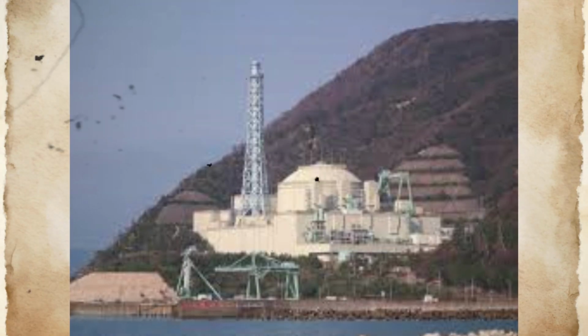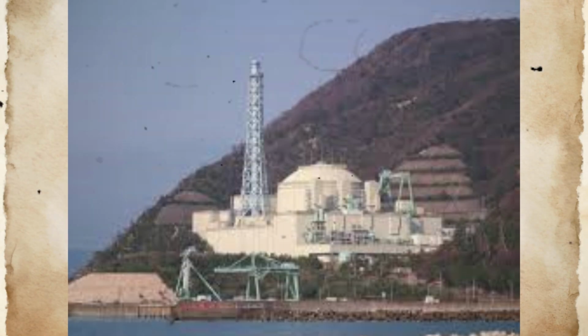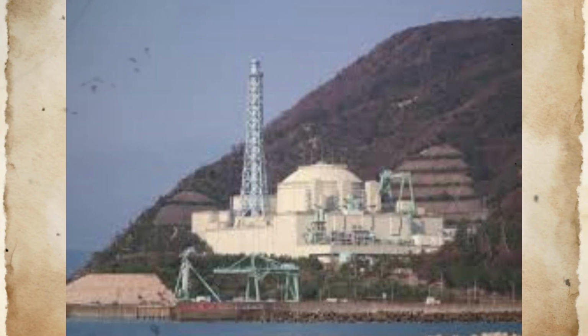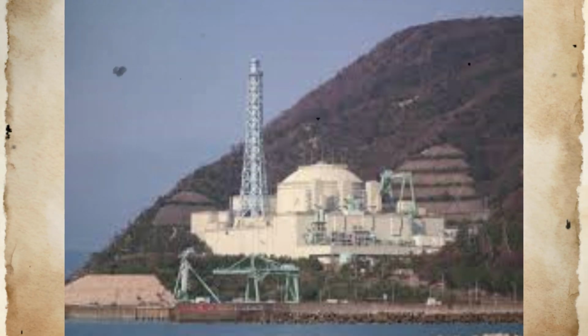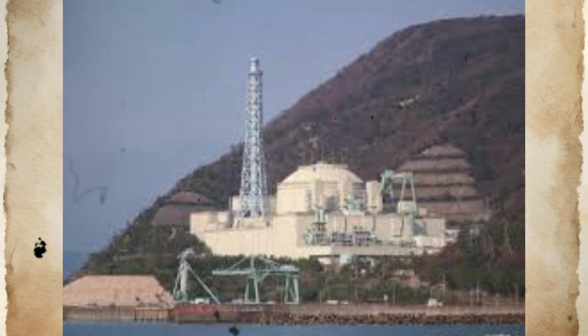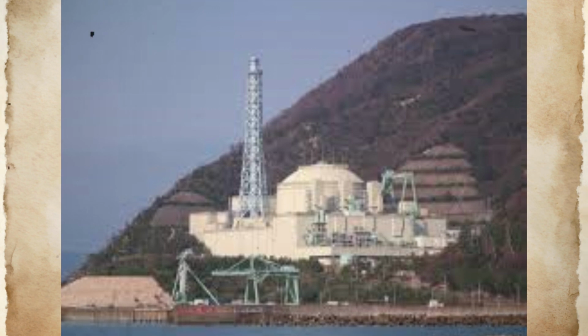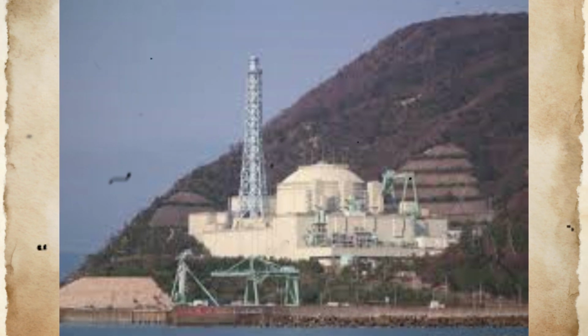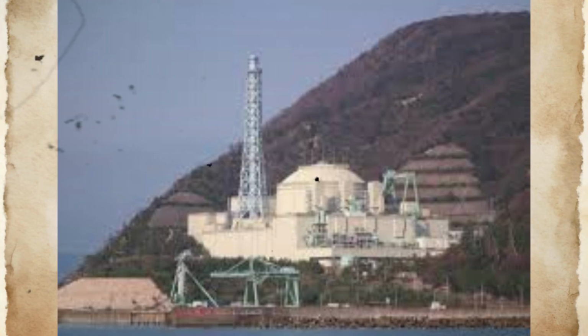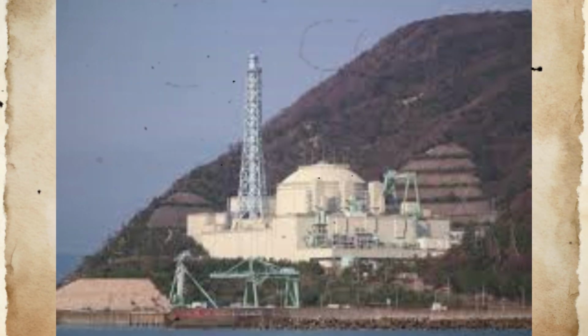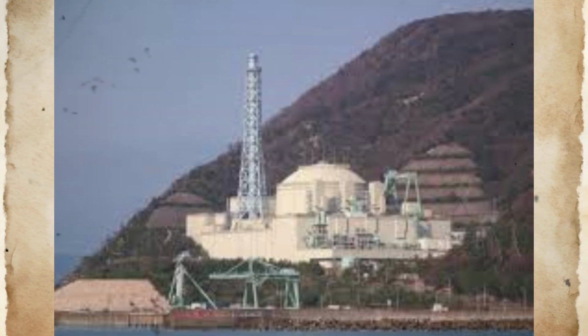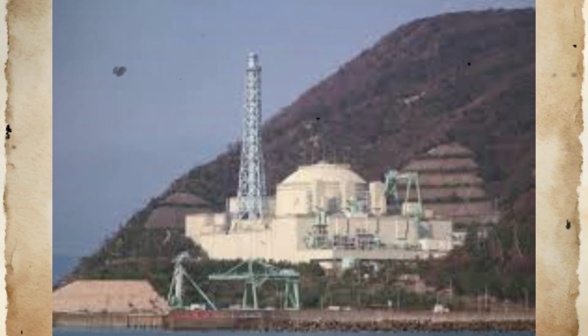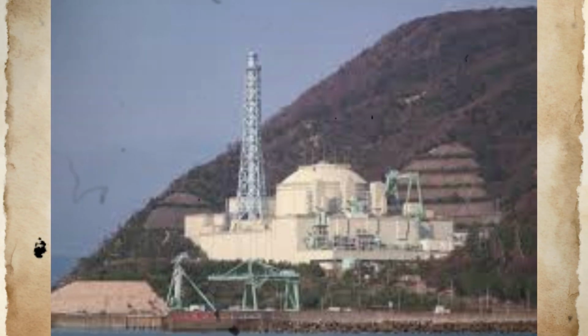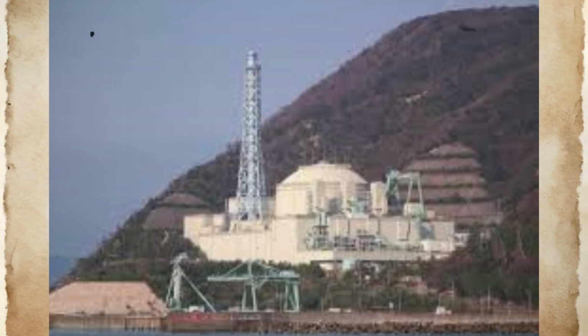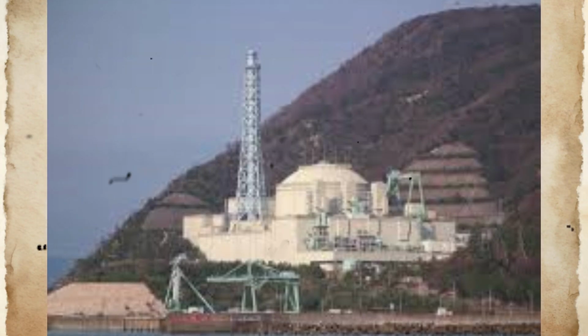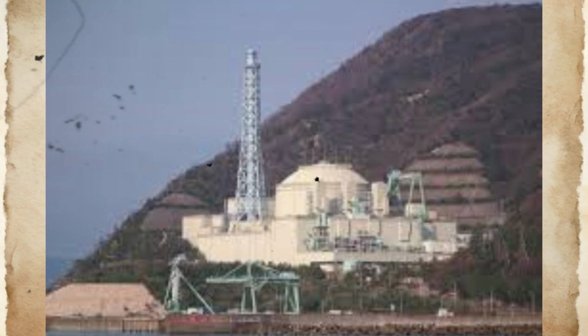The irregular geometry of the fatigue fracture surface created a complex flow path that influenced both flow rate and spray pattern of the escaping sodium. Computational fluid dynamics analysis conducted during the post-incident investigation revealed that sodium escaping through the fractured thermocouple well was ejected with sufficient velocity to distribute throughout the piping room. The high-temperature sodium immediately began oxidizing upon contact with atmospheric oxygen and moisture, creating the exothermic chemical reactions that generated heat, light, and gaseous products detected by the fire protection systems.